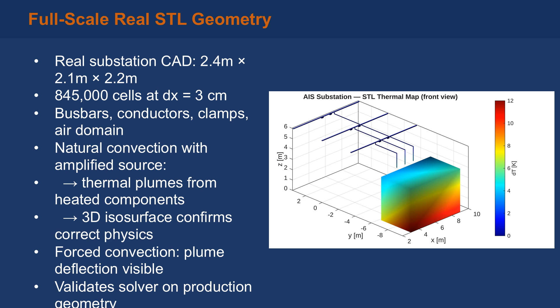The STL-mapped thermal field shown here confirms that the solver correctly resolves the individual busbars, conductors, clamp supports, and the transformer envelope as distinct heated features. Thermal plumes rise physically from heated components. The front view clearly shows the three-phase bus structure above the transformer tank.